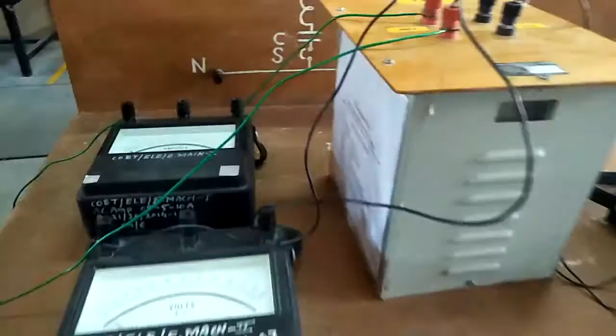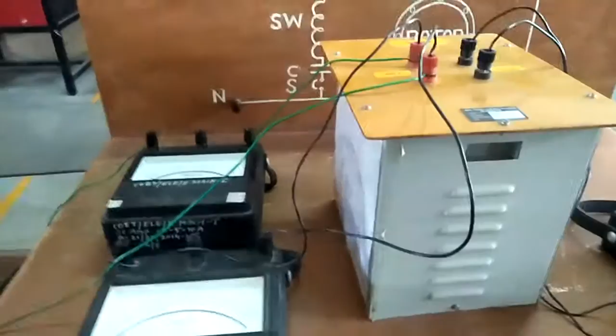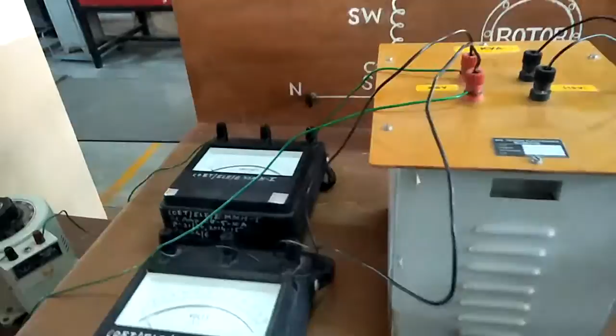Now we will connect a load on the secondary side because we want to test the current ratio. Current ratio can only be observed when current is delivered by the transformer, so we will connect a load.